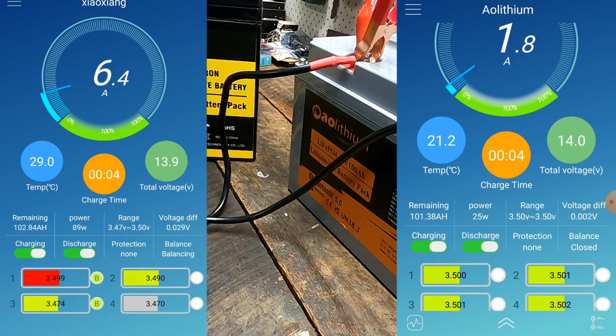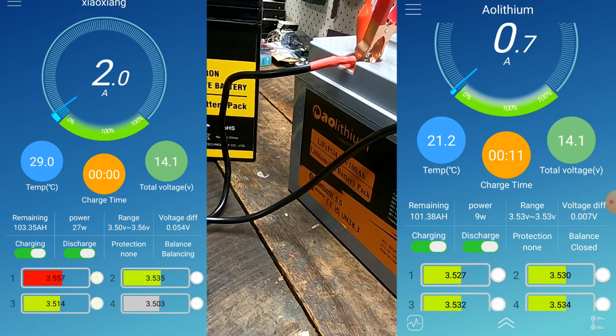We had 1 millivolt deviation in the AOLithium earlier, so 51 millivolt deviation in the Basin and only 6 millivolt in the AOLithium, because I did a full charge and discharge on the AOLithium last night after changing the settings. With this full charge again tonight, it actually balanced to under 5 millivolt already within the first charge cycle, with charge balance turned off.